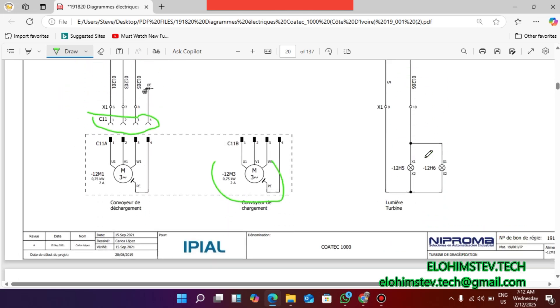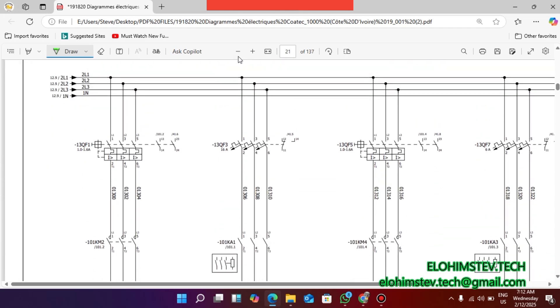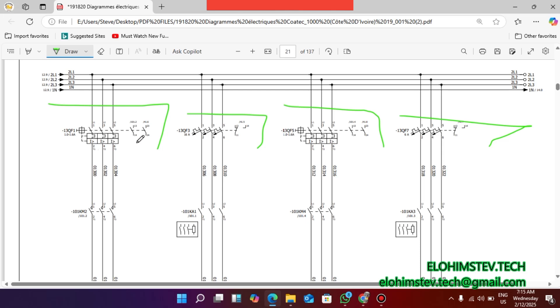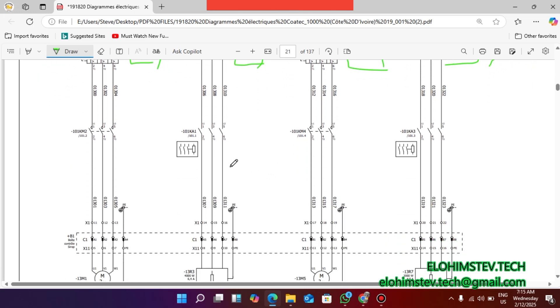This is also a circuit breaker, and we have multiple circuit breakers here. This circuit breaker, as I said, comes with auxiliary contacts. You see there are some differences: normally open, normally open, but this one comes with normally closed and then normally open. This one also comes with normally closed, normally open. This one is normally open, normally open. You have to take note of these and understand how they work before you can troubleshoot.